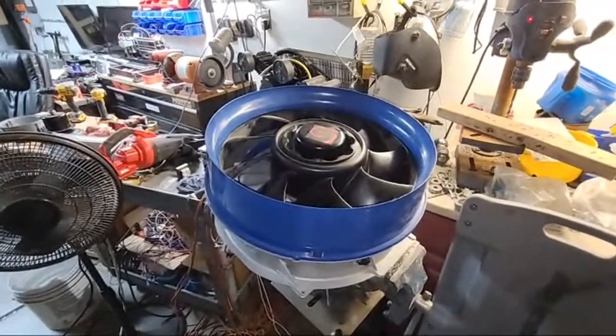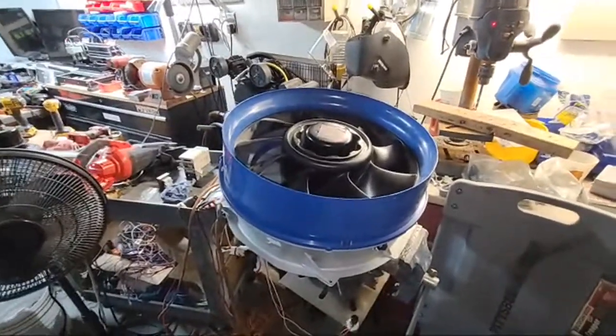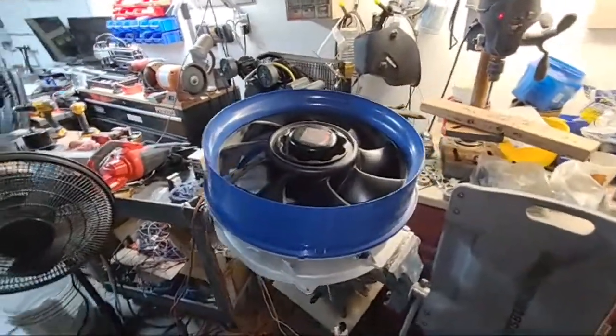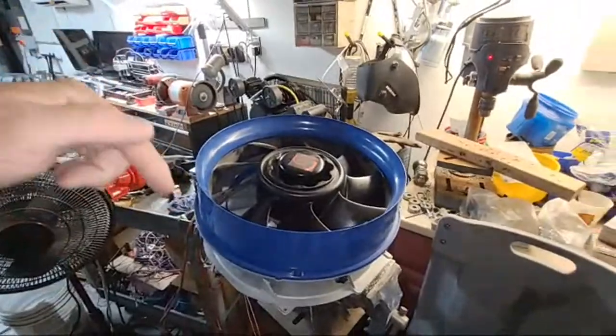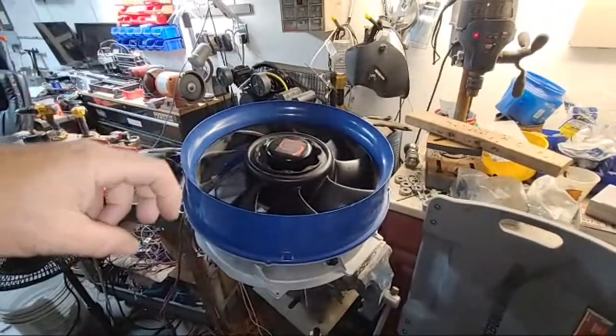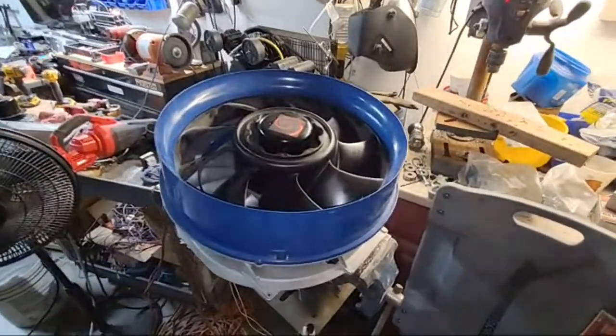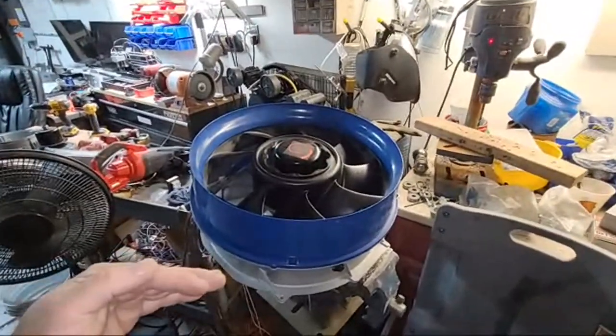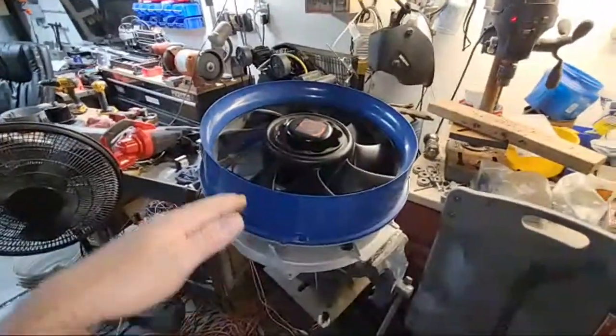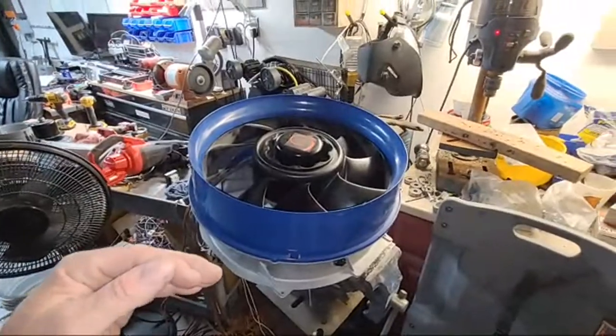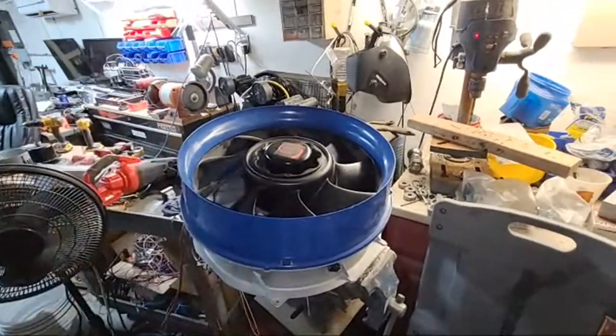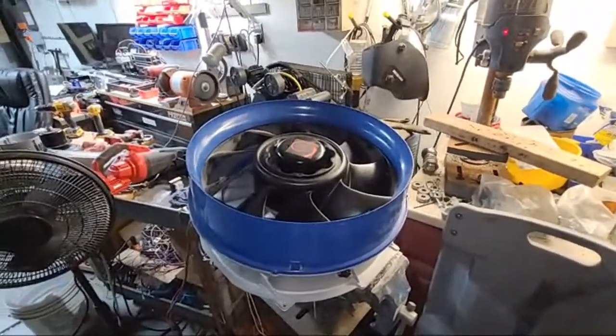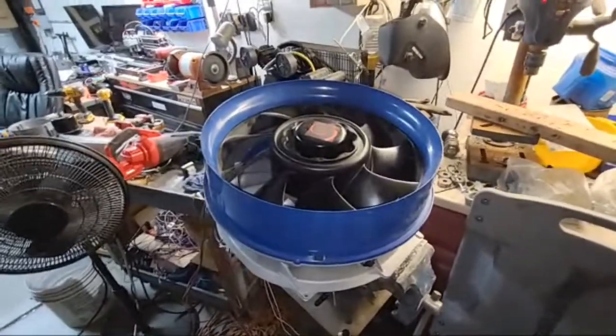So what they did in their infinite wisdom, and it sort of worked, but it throws you off as a tech until you realize it, they put a heater strapped in with the expansion valve sensing bulb. When that first high pressure switch trips, which is lower than the one that cuts out the whole unit, it closes a circuit, sends 24 volts through the heater, and heats up your expansion valve to open it up. That would be like, say, if you broke a belt or something like that.